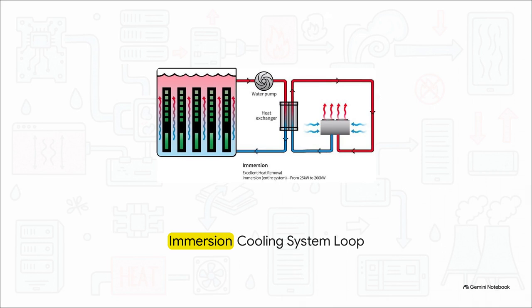This brings us to the extreme end of the spectrum: immersion cooling. I know it sounds a bit like science fiction, but it's happening right now. Instead of putting a cold plate on a chip, you take the entire server, motherboard, memory, processors, the whole shebang, and completely submerge it in a tank of liquid. Don't worry, this isn't tap water. This is a highly engineered, non-conductive, non-corrosive liquid designed specifically for electronics. The heat from the components naturally warms the liquid, making it rise, where it's then pumped out, refrigerated, and returned. This provides literally the most extreme heat removal possible and allows for incredibly dense computing in confined, non-traditional spaces.